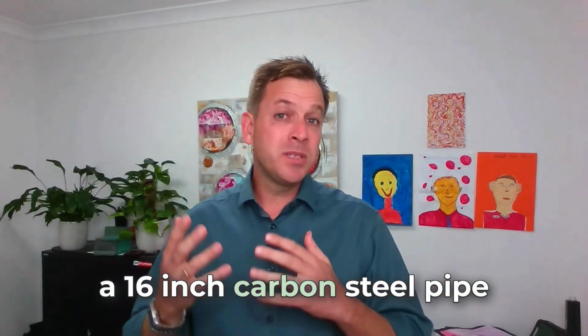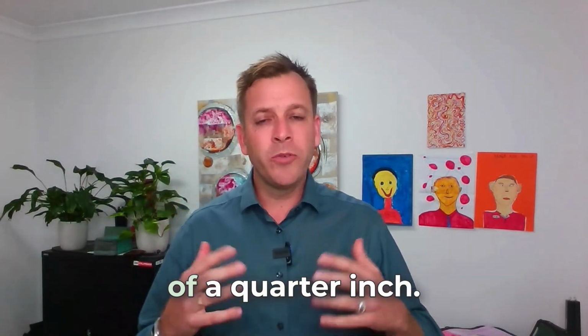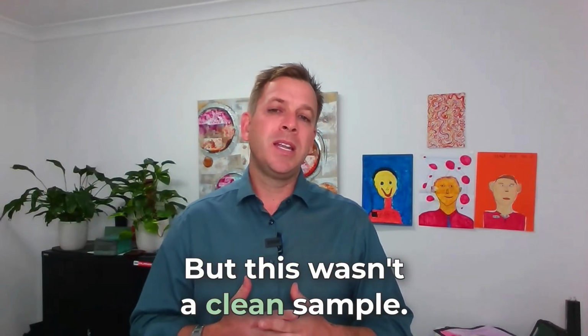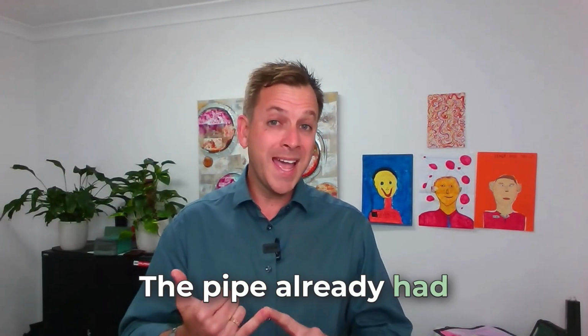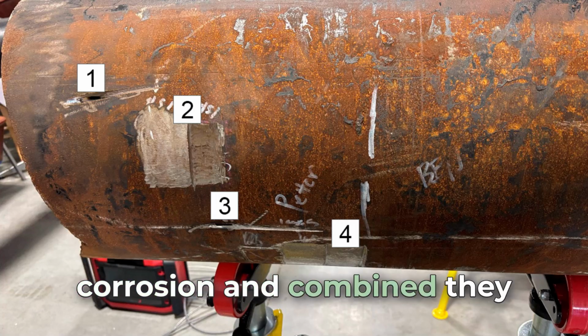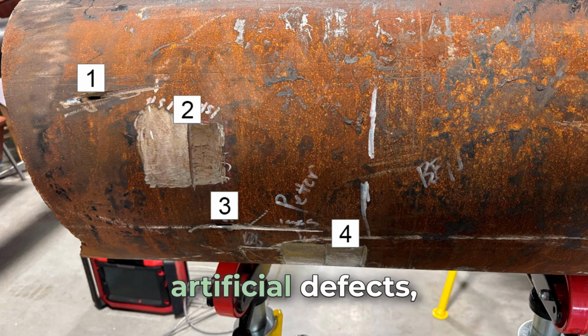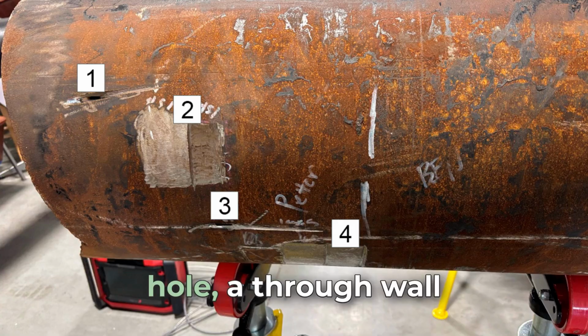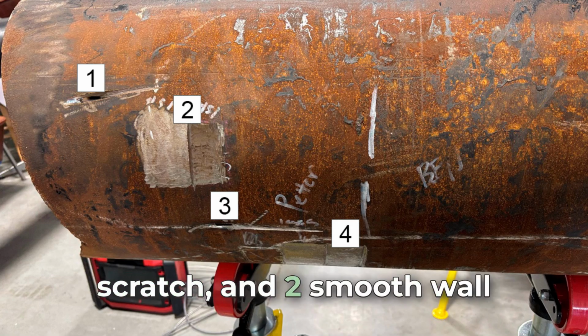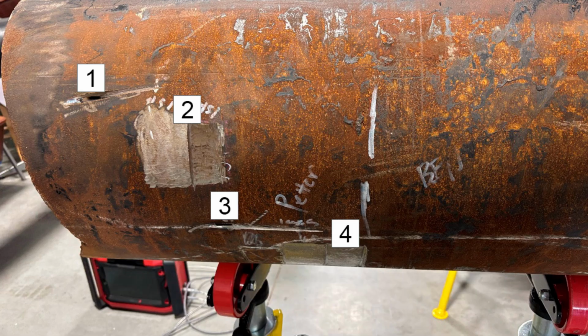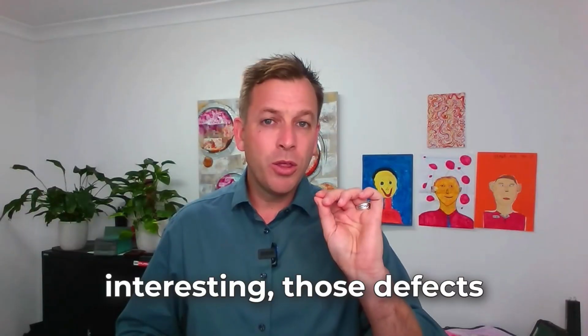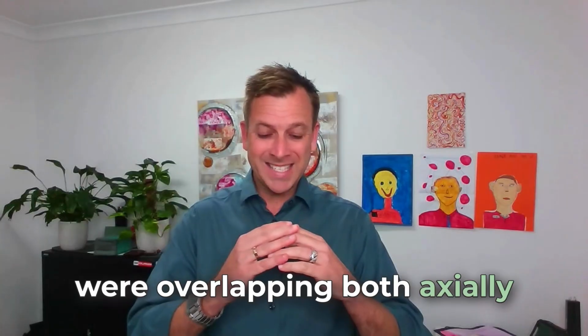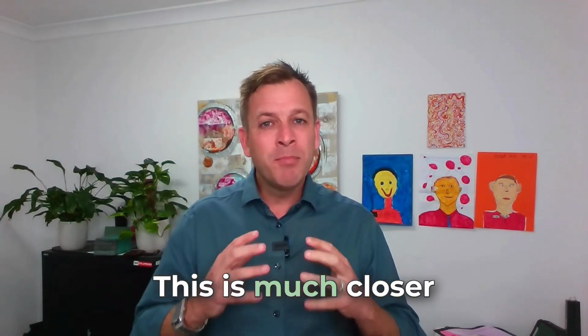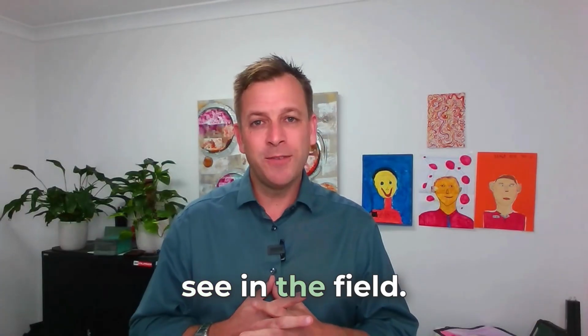Now this client had a 16-inch carbon steel pipe with a nominal wall thickness of 1/4 inch. But this wasn't a clean sample. The pipe already had generalized internal corrosion, and they combined that with 4 artificial defects, including a through-wall hole, a through-wall scratch, and 2 smooth wall reduction areas. And just to make things more interesting, those defects were overlapping both axially and circumferentially. So this isn't a best case scenario. This is much closer to what you'd actually see in the field.